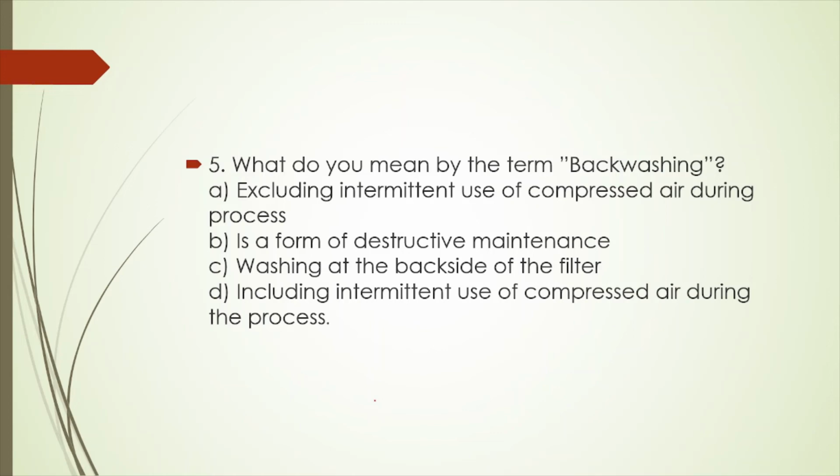Okay, so in backwashing, what do you do during water treatment in sewage plants or water purification? You just pump the water backward through the filter media, sometimes including intermittent use of compressed air. Alright, backwashing is a form of preventive maintenance so that the filter media can be reused. So it is basically a sort of preventive maintenance so that you can use the filter media.